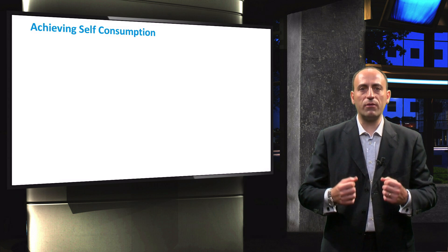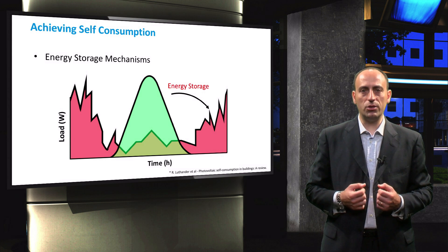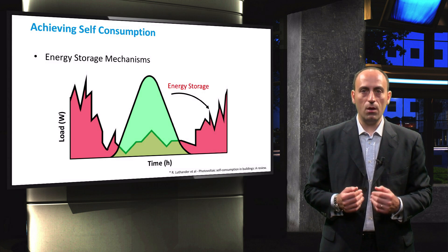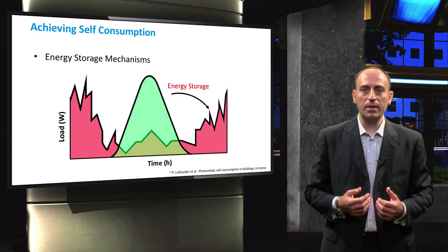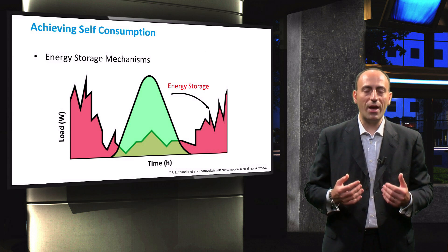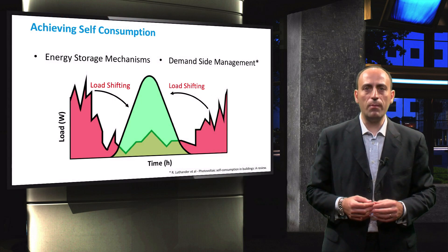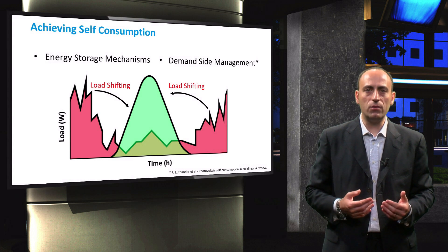So how can increased self-consumption be achieved? There are two main ways. The first option is to deploy energy storage, such as batteries. In that way, the overproduction can be stored locally, instead of being fed into the grid. With large enough storage capacity integrated into the PV system, the energy availability of the PV system can meet the load demand, reducing the interaction with the electricity grid. The second option to increase self-consumption is through demand-side management, or DSM. DSM makes use of the concept of load shifting, where the load demands of the household are shifted from time periods with surplus consumption to periods with surplus PV production. By adapting the load demand to the PV production pattern, self-consumption is increased further.